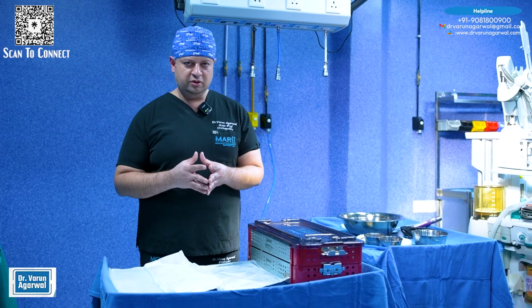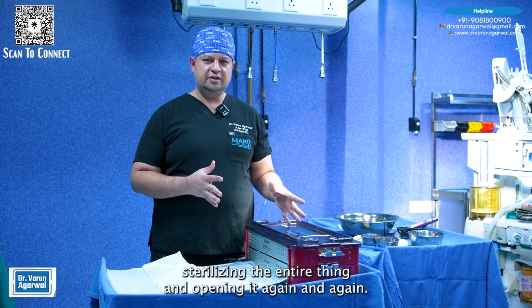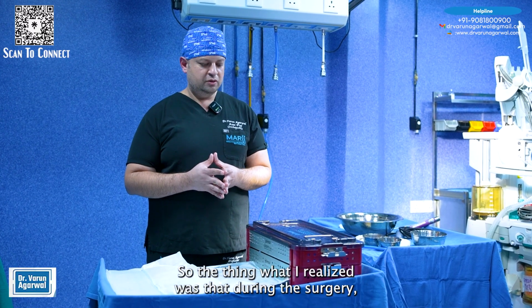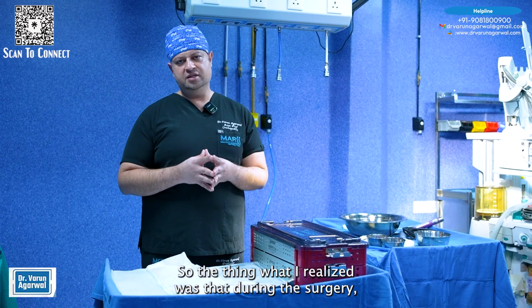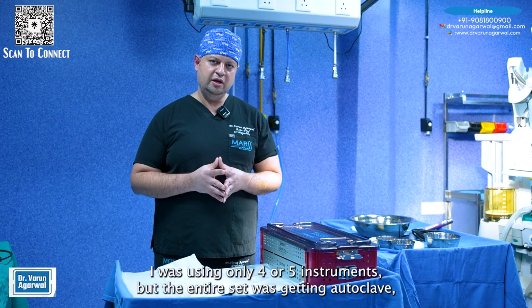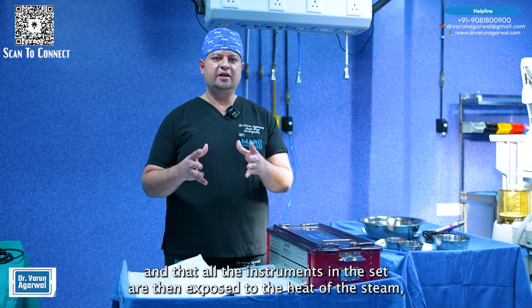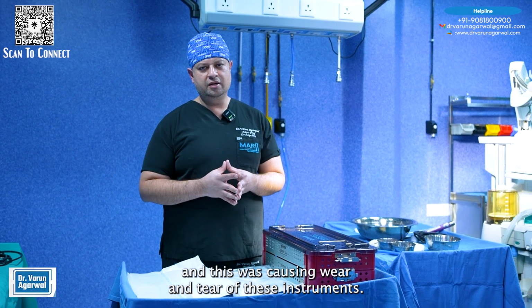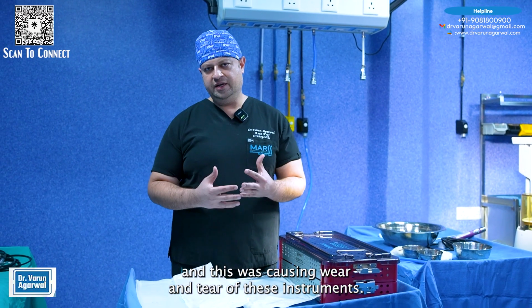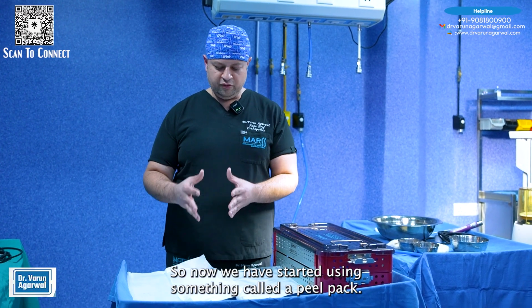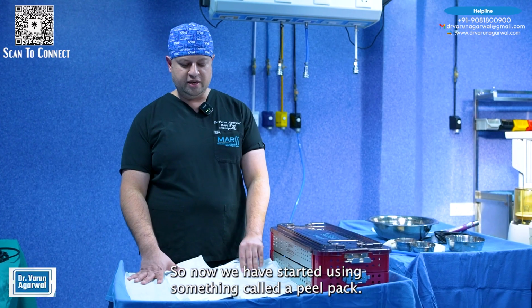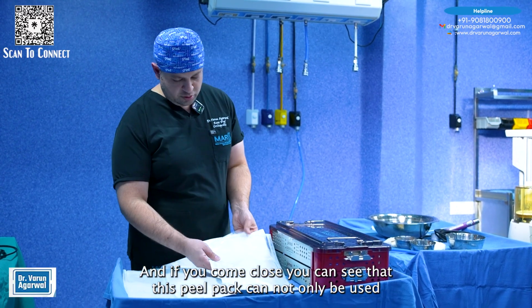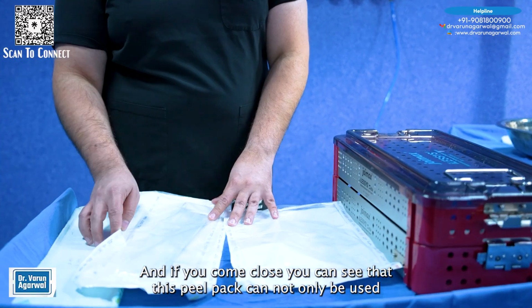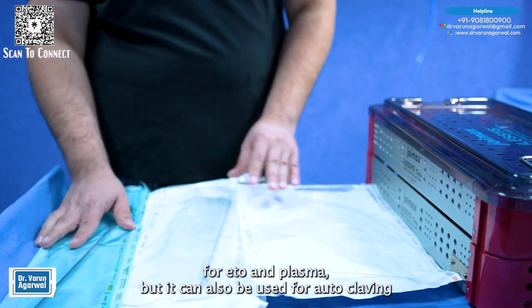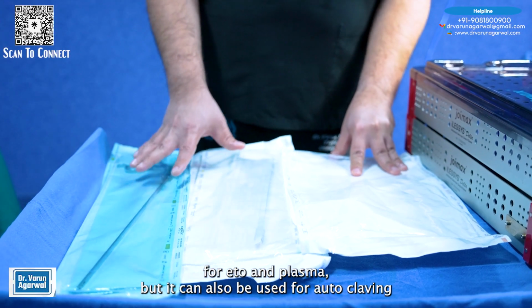So, to avoid sterilizing the entire thing and opening it again and again, what I realized was that during the surgery I was using only 4 or 5 instruments, but the entire set was getting autoclaved, and all the instruments in the set were exposed to the heat of the steam, and this was causing wear and tear of these instruments. So now we have started using something called a peel pack. This is a peel pack, and if you come close, you can see that this peel pack can not only be used for ETO and plasma, but it can also be used for autoclaving.